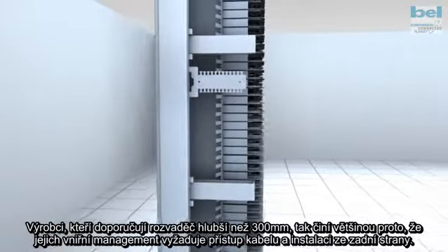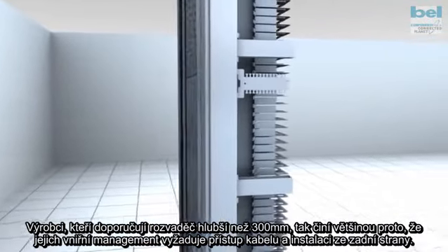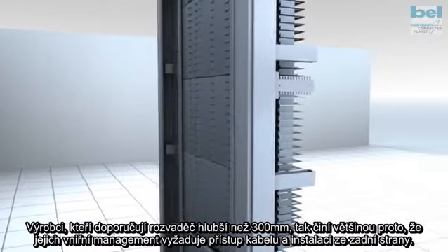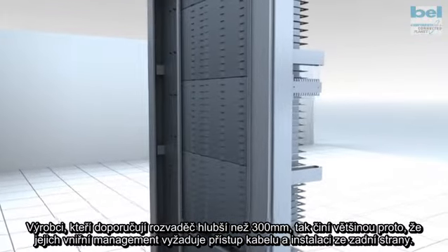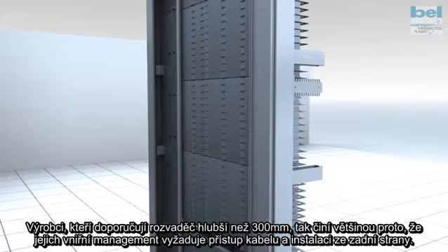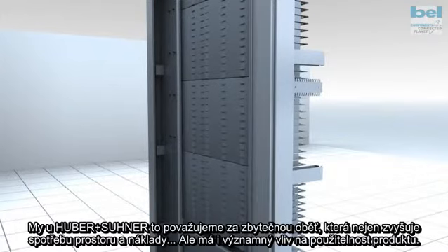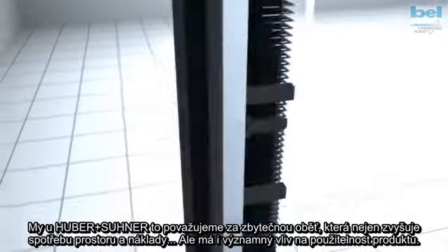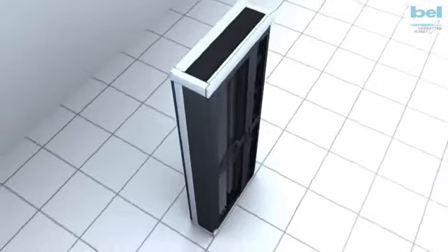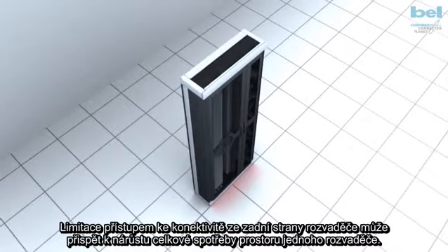Manufacturers who recommend a cabinet deeper than 300 millimeters generally do so because their internal connectivity platform requires cable access and installation from the rear side. At Huber+Suhner, we consider this to be an unnecessary sacrifice, which not only adds to the footprint size and cost, but has a significant impact on the usability of the product. The limitation of having to access connectivity from the rear side of the cabinet can often contribute still further to the overall space consumption of a single cabinet.